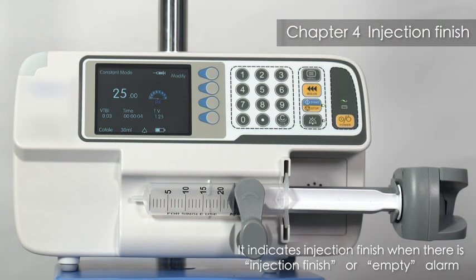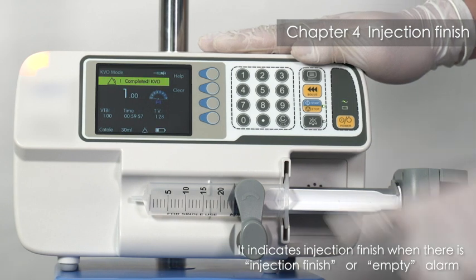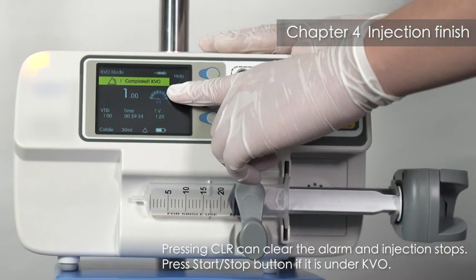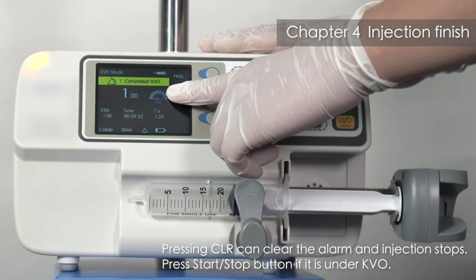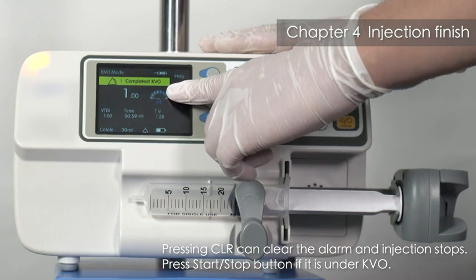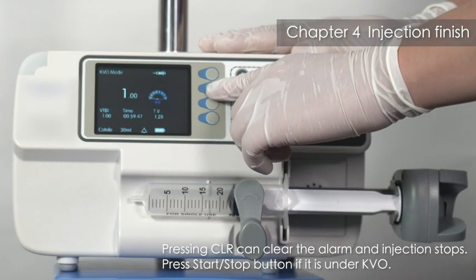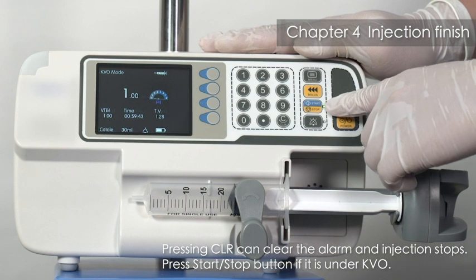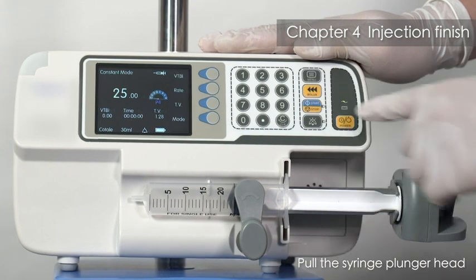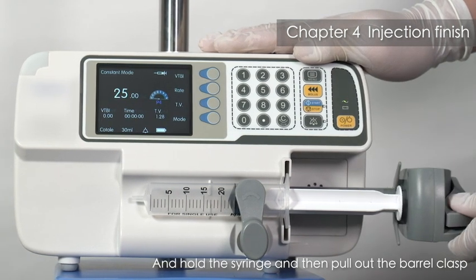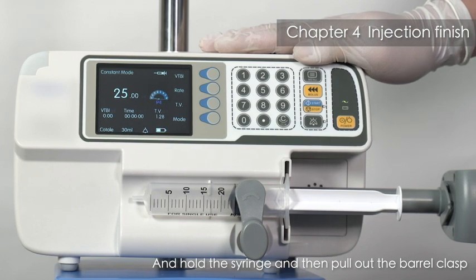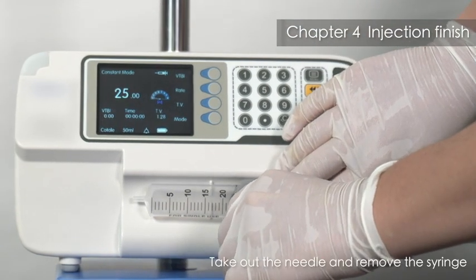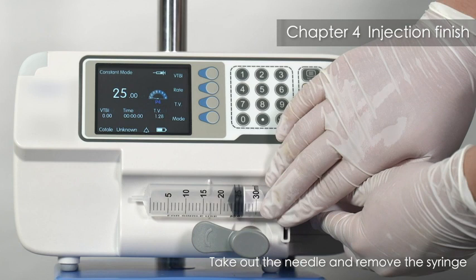It indicates injection finish when there is injection finish or empty alarm. Pressing CLR can clear the alarm and injection stops. Press Start, Stop button if it is under KVO. Pull the syringe plunger head and hold the syringe, and then pull out the barrel clasp. Take out the needle and remove the syringe.